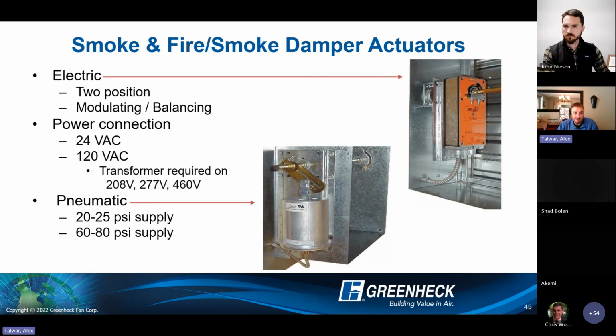Typically, actuators these days are electric, 24, 120 volts, something like that. Usually we'll see transformers for anything higher. Two position actuator, just open and close, or we do have modulating capabilities for actuators as well. They're not exactly cheap, but if you do want to be able to hook that fire smoke damper up to some type of modulating control, give it a 2 to 10 or 0 to 10 volt set point signal, or hook it up to an airflow set point and modulate your damper, we do have those capabilities.